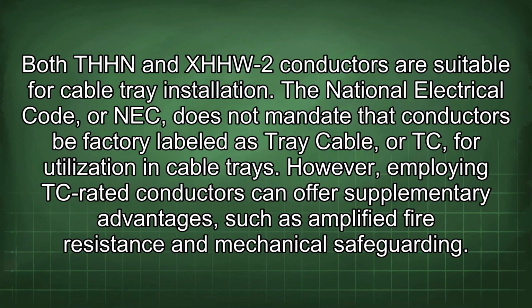Both THHN and XHHW-2 conductors are suitable for cable tray installation. The National Electrical Code, or NEC, does not mandate that conductors be factory labeled as tray cable or TC for utilization in cable trays. However, employing TC-rated conductors can offer supplementary advantages such as amplified fire resistance and mechanical safeguarding.